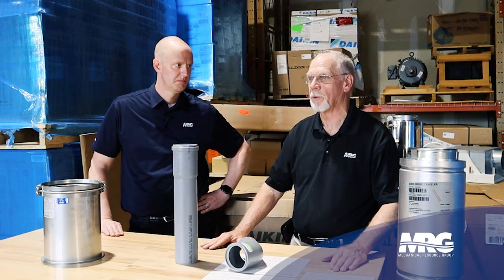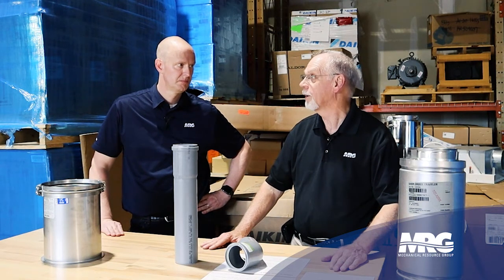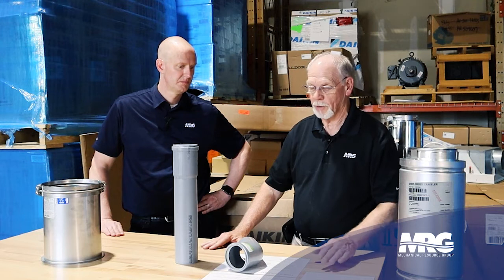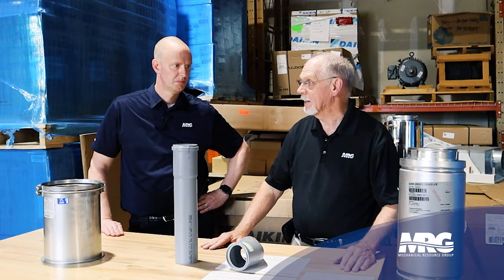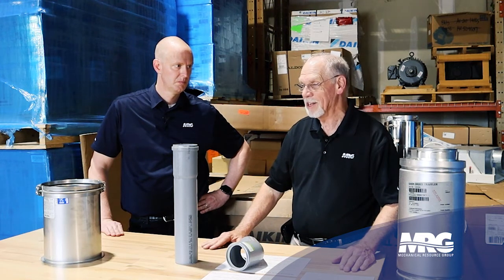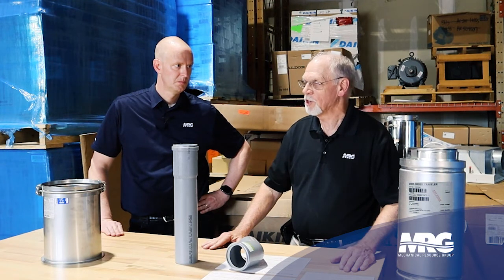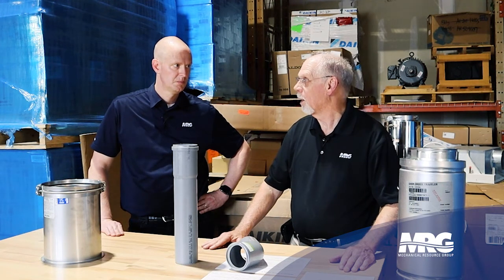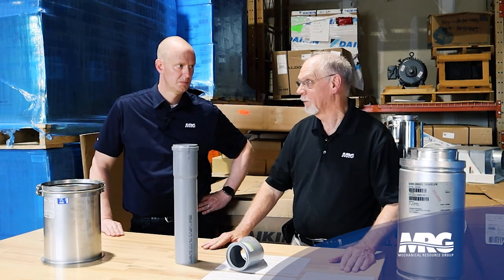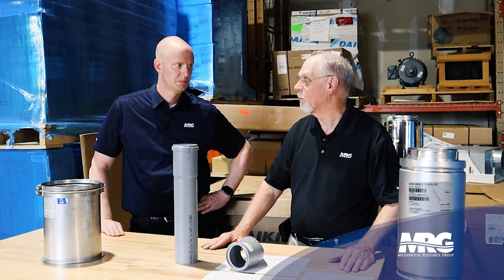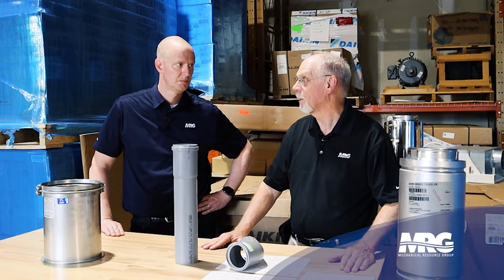You can have a fan that will push the flue gas out, or you can have one on the very top of the roof that will pull it out. But that's based on what your length of your vent piping is. The other thing you talked about on multiple appliances, it's very, very critical to have the engineered system when you have multiple appliances, and all the piping has to be compatible. You can't have mixed piping when you have multiple pieces. They all have to have the same pipe system so that they can be connected properly.